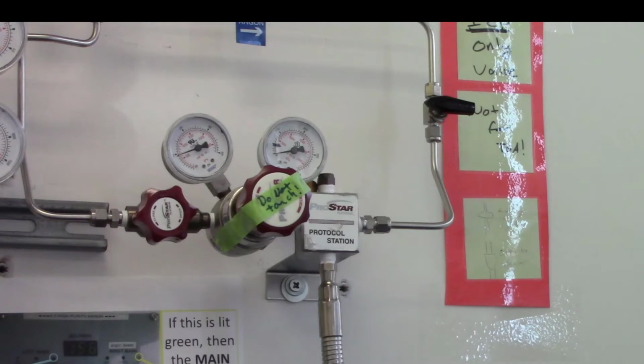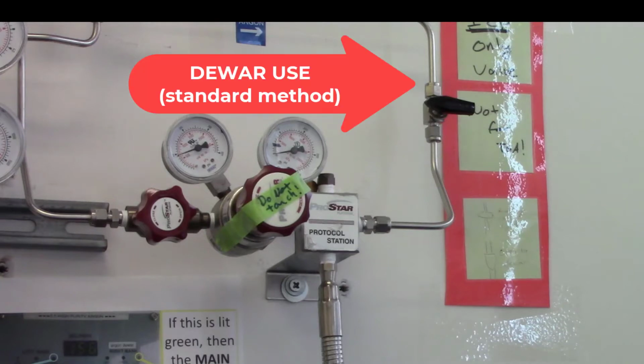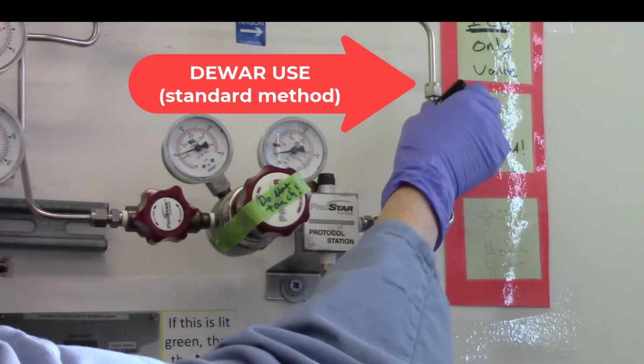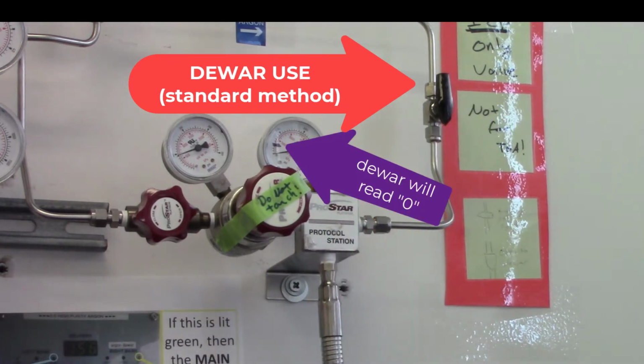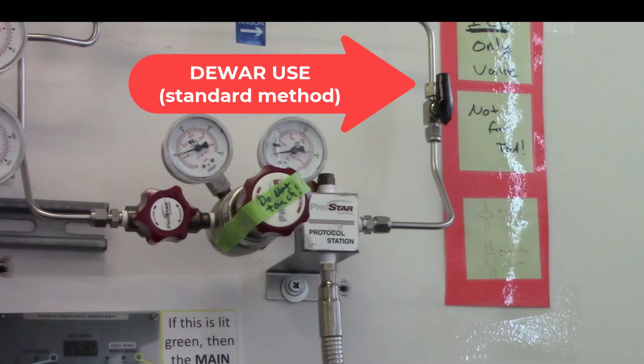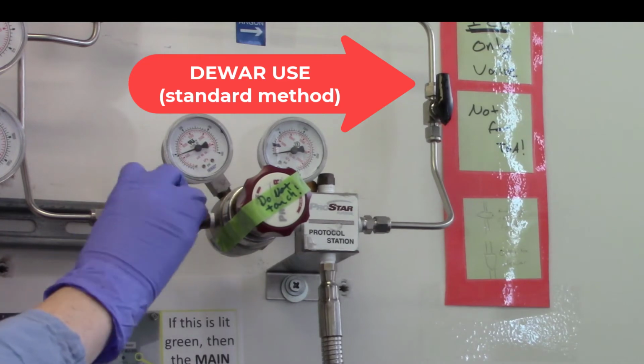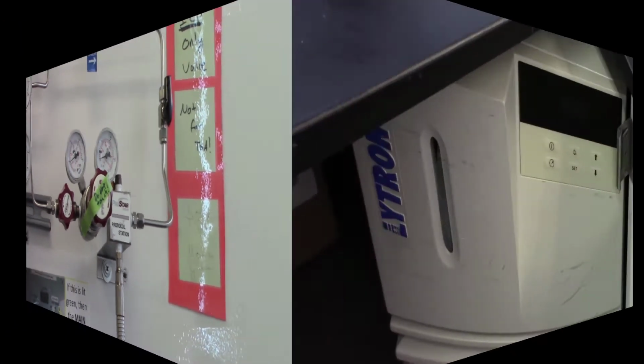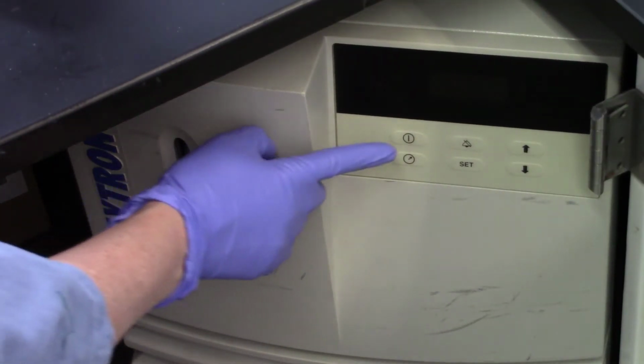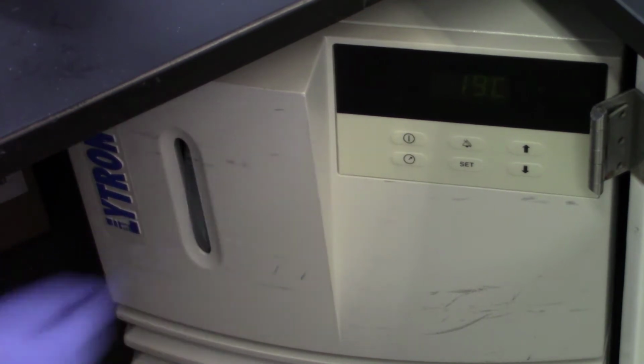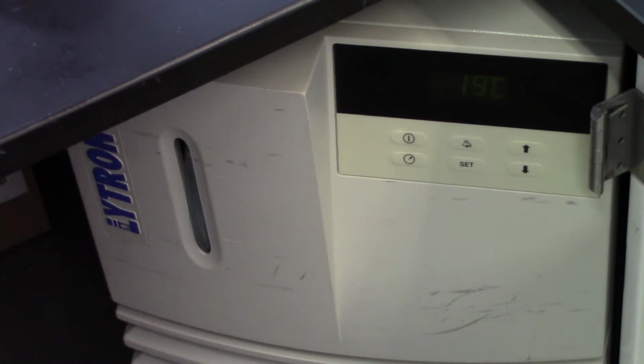After confirming that the dewar has enough gas, open the black valve on the right. The delivery pressure from the dewar is low enough that it won't register on the regulator, but this is okay. Next, be sure the knob on the left is turned to the open position. Now locate the chiller under the computer and turn it on by pressing the button in the upper left. Within a few minutes, the temperature will reach 19 degrees Celsius.